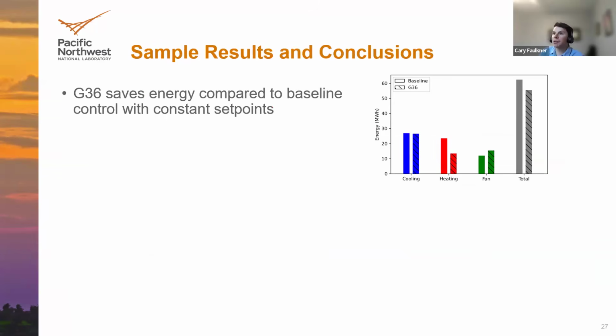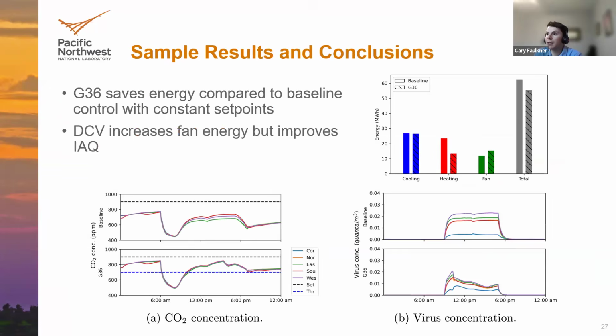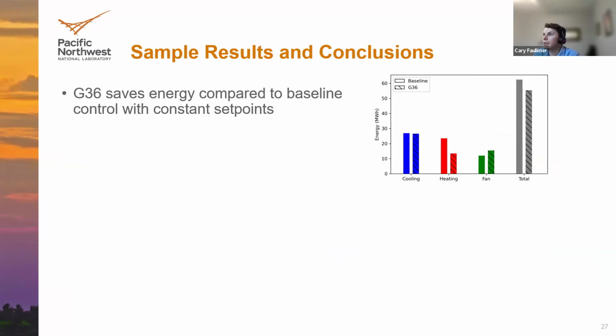And then just quickly, some of the results from this. We found that the Guideline 36 controls can save energy compared to the baseline control, which just used constant set points for this VAV system and the hot water and chilled water plants. In particular, it is able to save a good amount of heating energy, I think by avoiding reheat, particularly by resetting the supply air temperature set point, and maybe also a little bit of cooling energy.